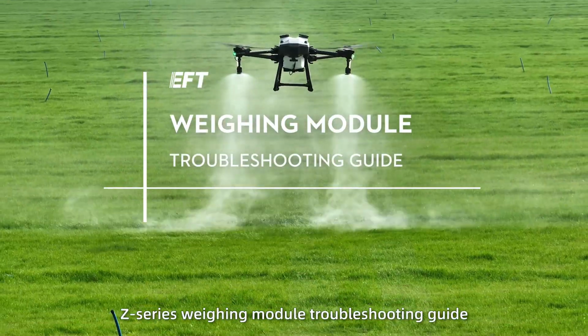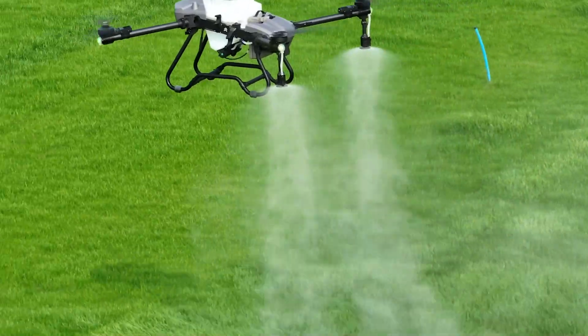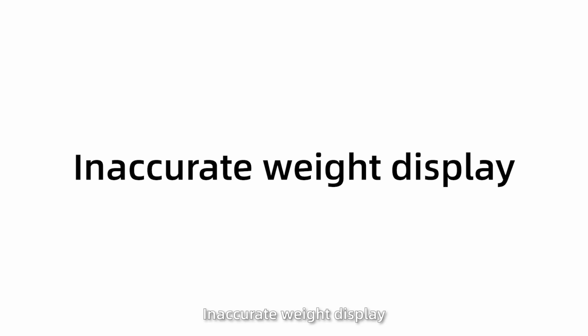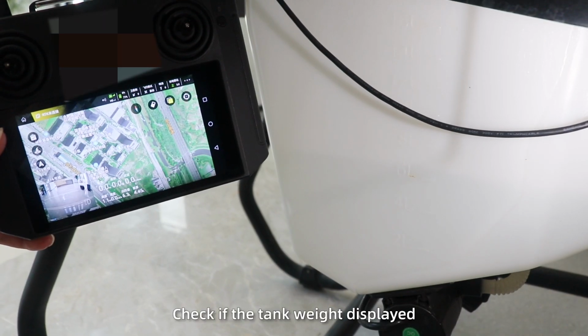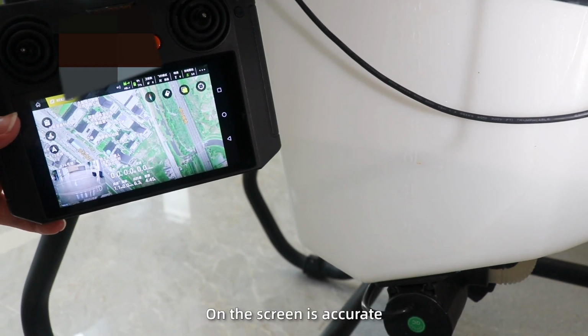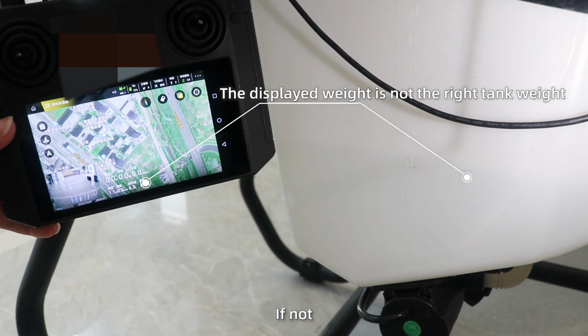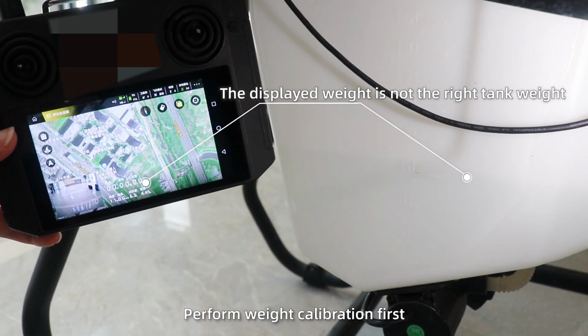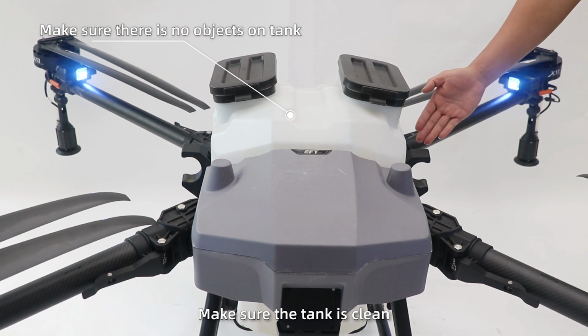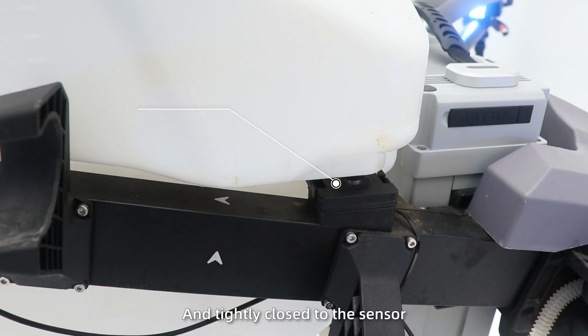Z-series Weighing Module Troubleshooting Guide. Situation 1: Inaccurate weight display. Check if the tank weight displayed on the screen is accurate. If not, perform a weight calibration first. Make sure the tank is clean and tightly close to the sensor.